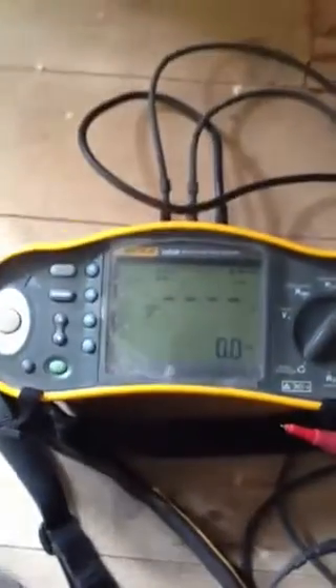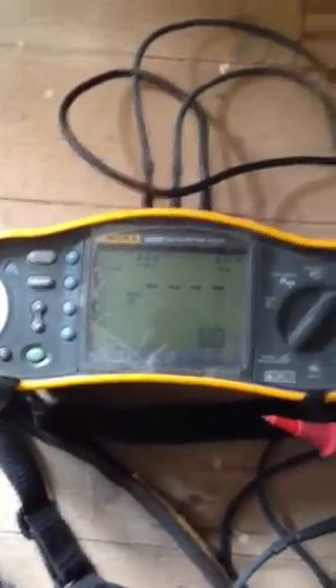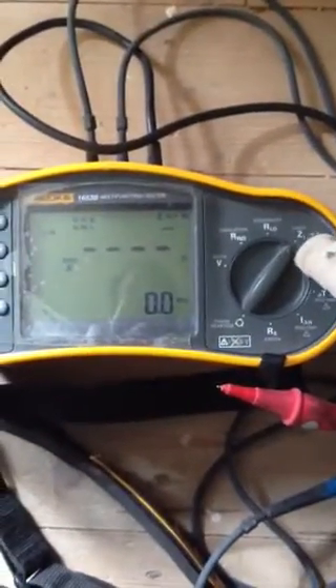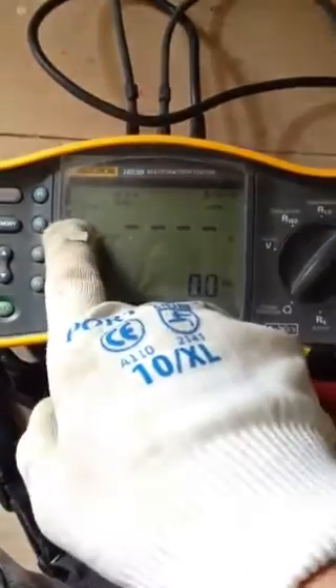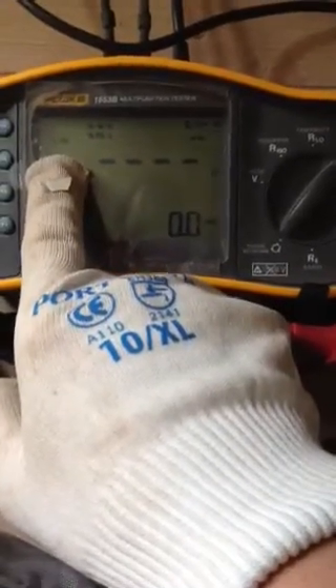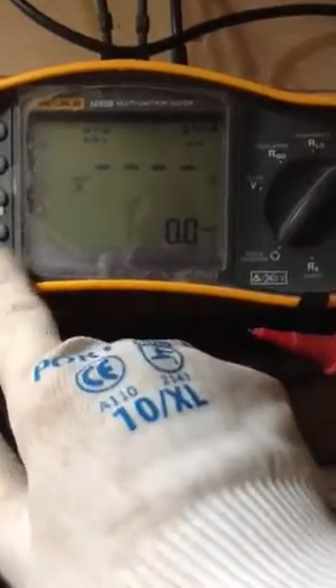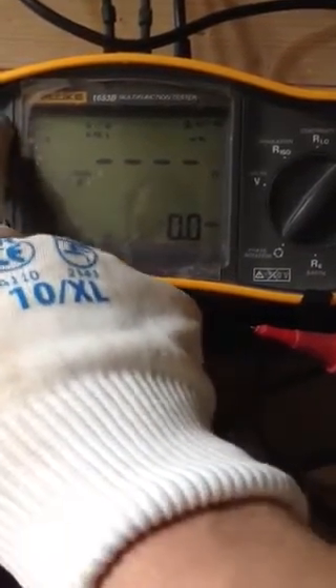Carrying out the earth fault loop impedance test using the Fluke 1653B, we obviously need to select loop on the tester, and ensure that we've got L-PE selected here. That's the earth. We can change it to prospective short circuit current, which we're not really interested in at the moment. It requires a 3-lead test, so we need 3 leads connected into the unit.